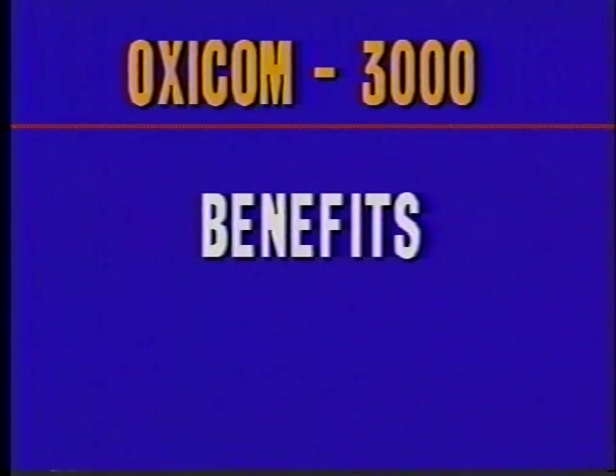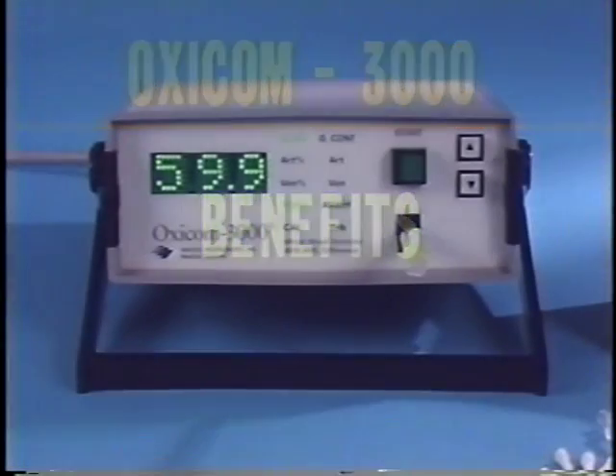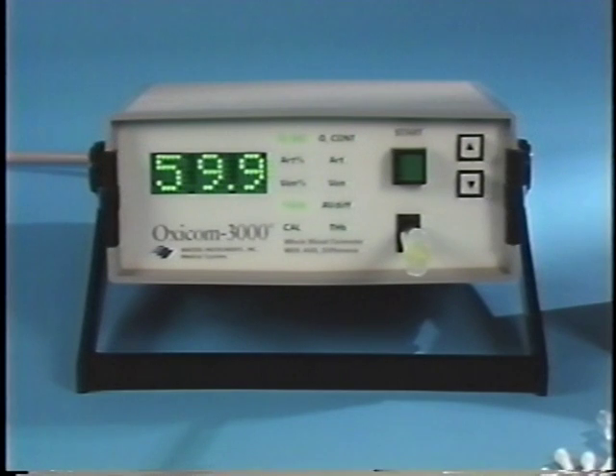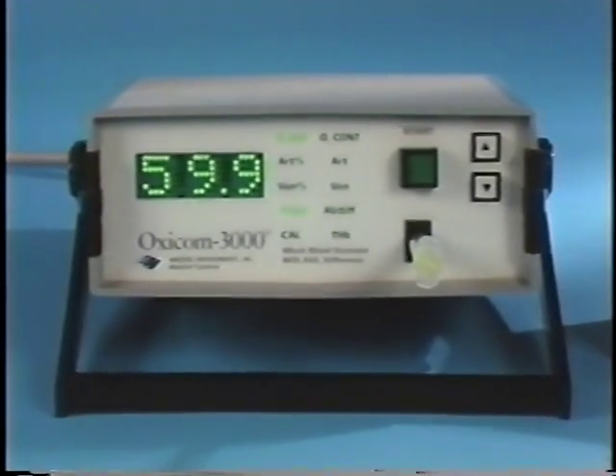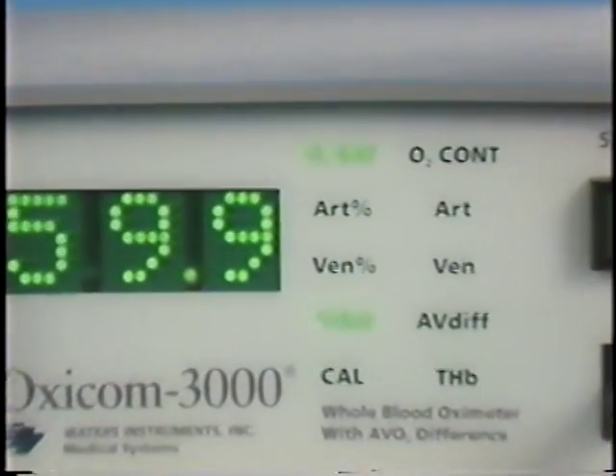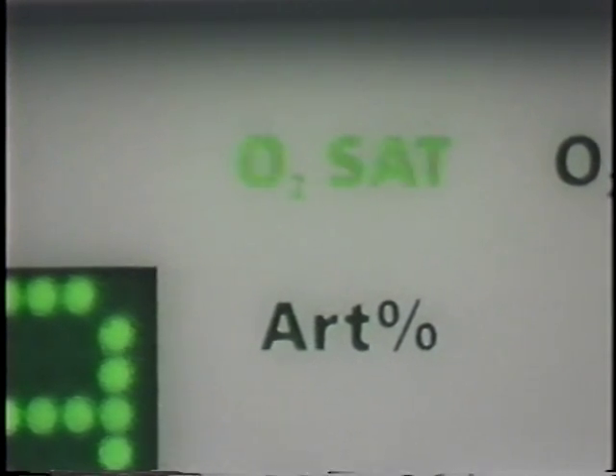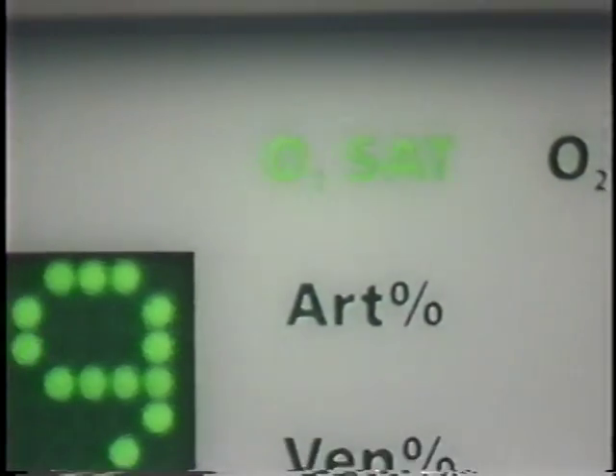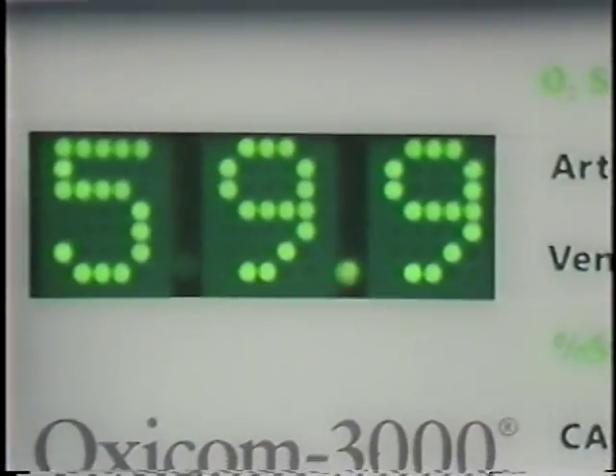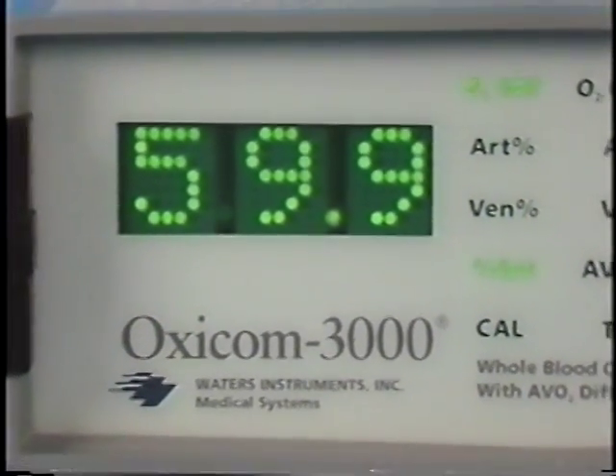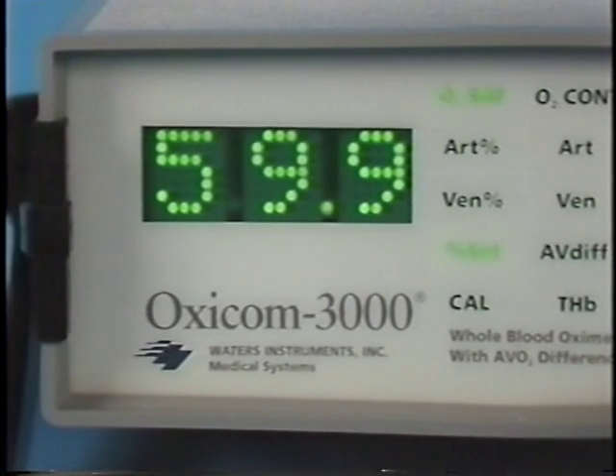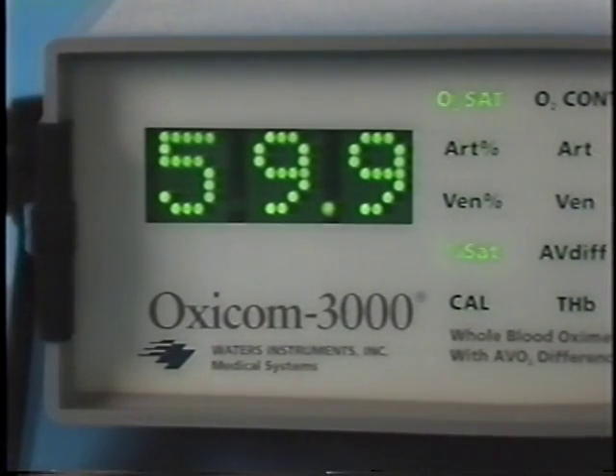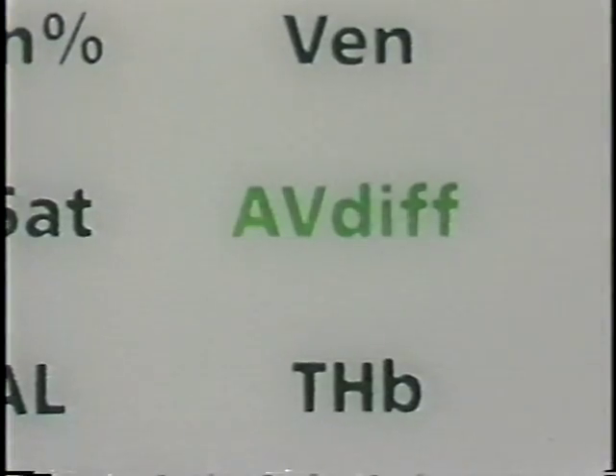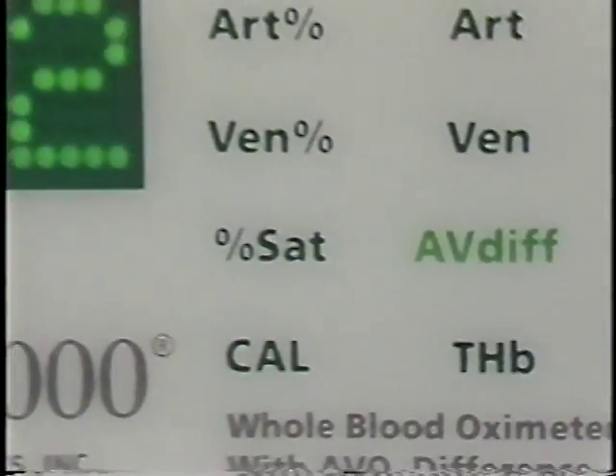Benefits. Oxicom 3000 benefits include fiber optic technology and a solid-state detector, proven in the Oxicom 2000, that provides you with accurate and repeatable measurements. In the oxygen saturation mode, the 3000 will provide results on the measurement display in less than 10 seconds. For convenience and accuracy in determining cardiac output by the Fick method, the Oxicom 3000 calculates oxygen content of the arterial and mixed venous samples and computes AVO2 difference.